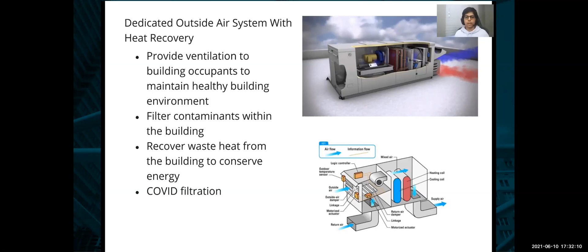We are also going to be using an active chilled beam system, and although the name suggests the word chilled, we are going to be using them as a heating device. In these beams, we have heated and chilled water running through in order to provide rooms with cool or warm air during convection. What makes these an active chilled beam is that it uses clean DOAS air from the slide before and uses that air to give the occupants of the room clean air to breathe. In the second image, we can see the nozzles that show the clean DOAS air.